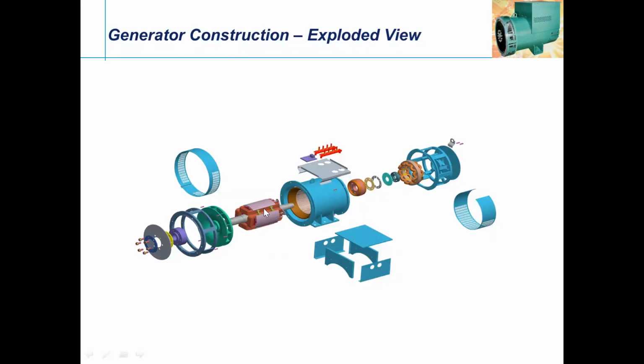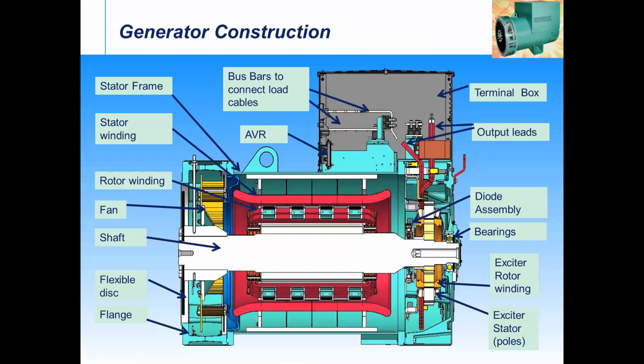There is a main rotor and main stator winding. This is a terminal box where the output lead can be connected to the terminal bars. And of course, there is an exciter, which we will discuss in the excitation system. And there is an RRA, rotating rectifier assembly, in the small parts, and the ND shield, which is holding the bearing. So this is the exciter stator, which will be a two-machine system, which we will discuss during this part. So this is where the generator construction starts, like what you have seen.